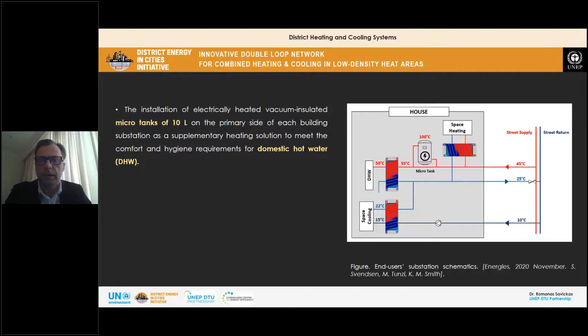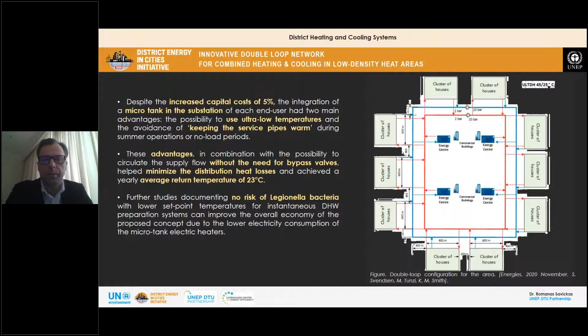Despite increased capital cost, about 5%, from the integration of a micro tank in the substation of each end user, you have two main advantages. First of all, the possibility to use ultra low temperatures and avoidance of keeping these service pipes warm during the summer operation or no load periods. Also, the possibility to circulate the supply flow without the need for bypass valves. This helped to minimize the distribution heat losses and achieved an average return temperature of about 23 degrees, which is quite a good result. Further studies documenting no risk of Legionella bacteria with lower set point temperatures for this domestic hot water preparation system can be found.